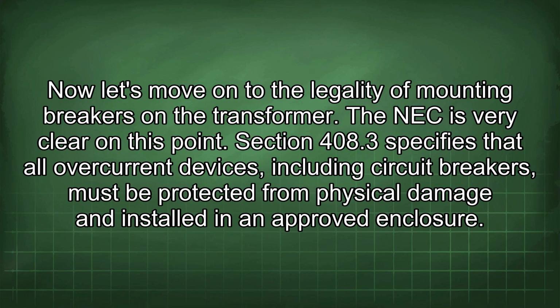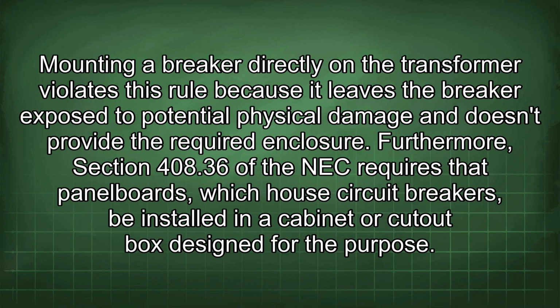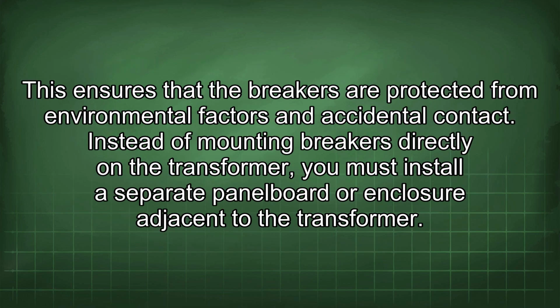Section 408.3 specifies that all overcurrent devices, including circuit breakers, must be protected from physical damage and installed in an approved enclosure. Mounting a breaker directly on the transformer violates this rule because it leaves the breaker exposed to potential physical damage and doesn't provide the required enclosure. Furthermore, Section 408.36 of the NEC requires that panel boards, which house circuit breakers, be installed in a cabinet or cutout box designed for the purpose. This ensures that the breakers are protected from environmental factors and accidental contact.